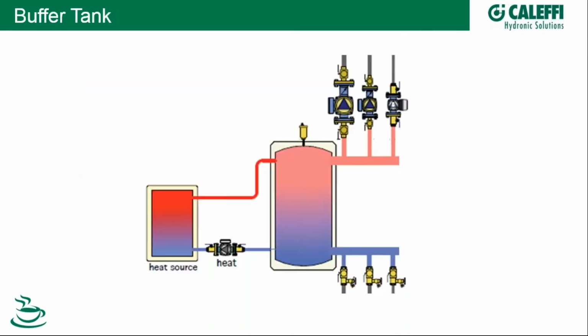The second of the 3 methods for decoupling pumps is buffer tanks, as you see here. I've taken the T's away and put a buffer tank in place. Now you wouldn't do this just for the sole purpose of decoupling. This 4-port hydraulic separator or buffer tank does perform decoupling or hydraulic separation, another term for decoupling, of these pumps over here. But the purpose of a buffer tank is to reduce the cycling that this heat source is going to experience, which is especially important in a highly zoned secondary, meaning you have several zones and at least a couple, 1 or 2 of those, even 1, with the heat load on that zone much smaller than the others.